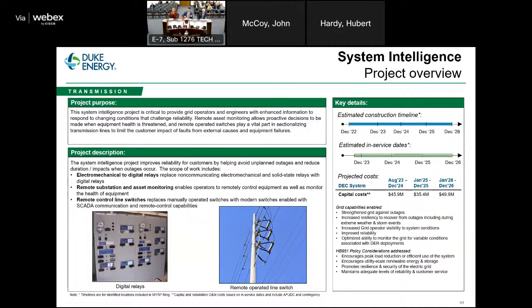Digital relays and remote operated sectionalizing switches. You see 2 pictures of those on the slide here. These are 2 of the scope areas. They really work in conjunction with each other. Digital relays, essentially what we're doing is we're removing a legacy relay design, which is an electromechanical device, cams, levers, springs. We're replacing that with a computer. And this computer is able to, of course, not only sense a fault, that's ultimately what it really does, is sense a problem on the grid and sends a signal to a circuit breaker to open, to isolate that problem.